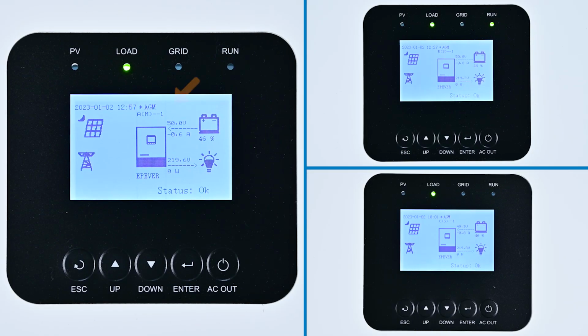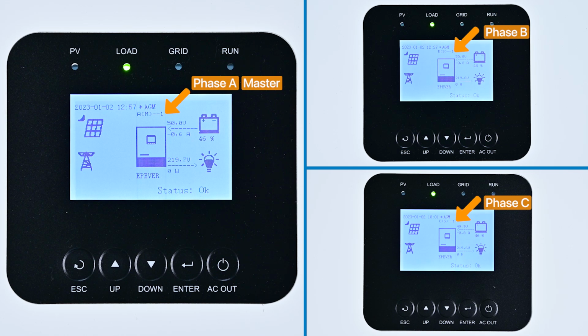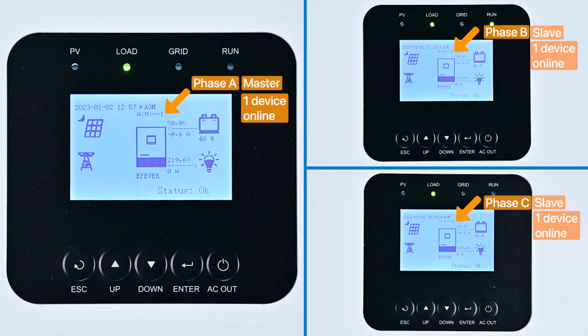You should see A, M, 1, B, S, 1, C, S, 1 on the displays, indicating the phase A, B, C of the output live wire, with M for the master device and S for slave devices. The number 1 signifies one device is online for each phase, matching the initial phase settings.